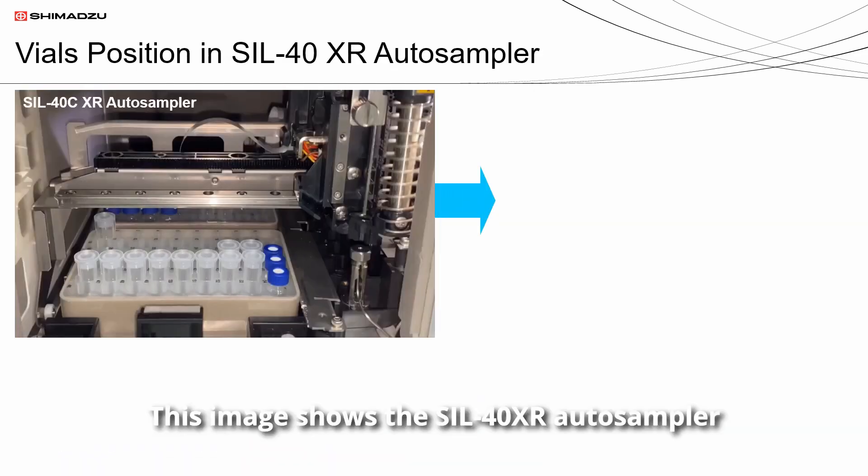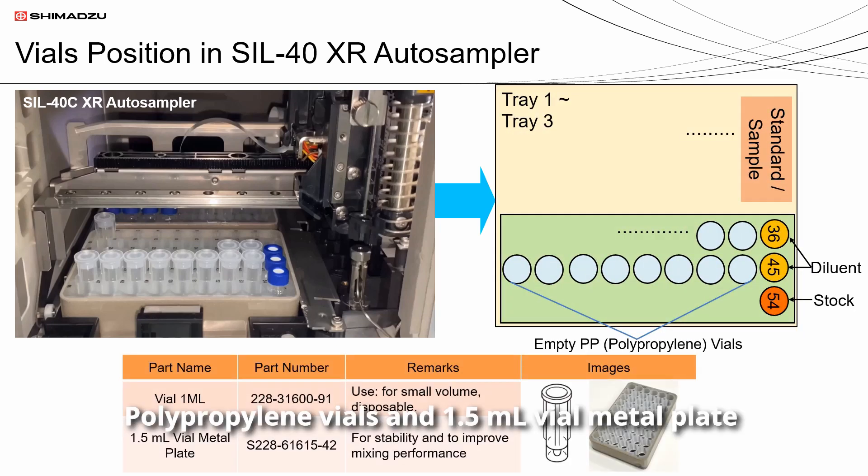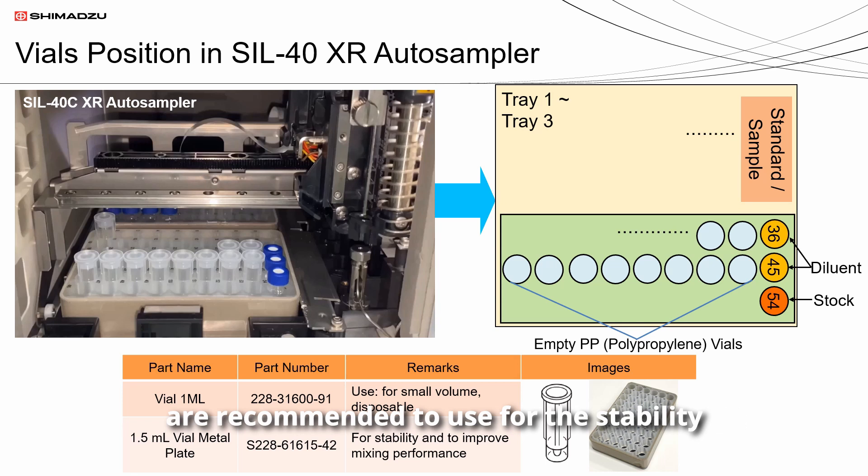This image shows the SIL-40C XR autosampler and the vials position. Polypropylene vials and 1.5 mL vial metal plate are recommended to use for stability and improved mixing performance during the automated dilution.